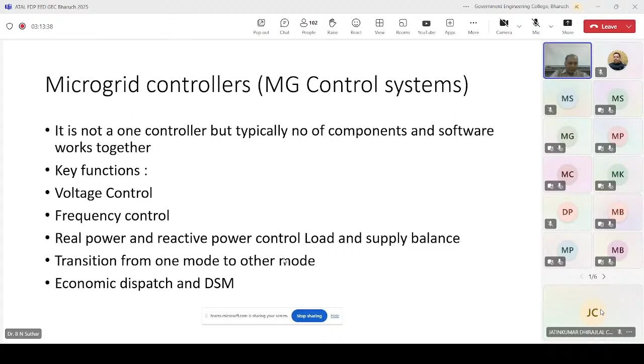Now, when we talk about the control and stability of microgrid, how it is different from the conventional one, we'll see. In microgrid, we have to control voltage, frequency, real and reactive power. We have to maintain the balance between load and generation, and we have two operating modes: grid connected mode and standalone mode. There should be a smooth transition between these two modes, and all these things should be operated economically.